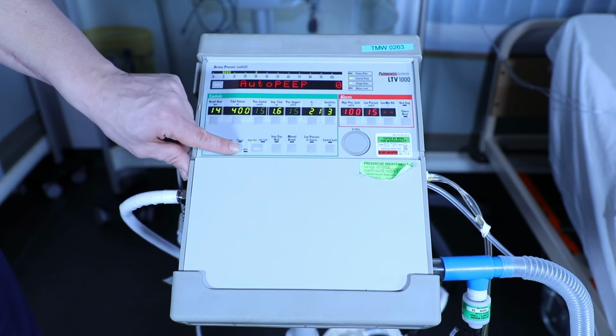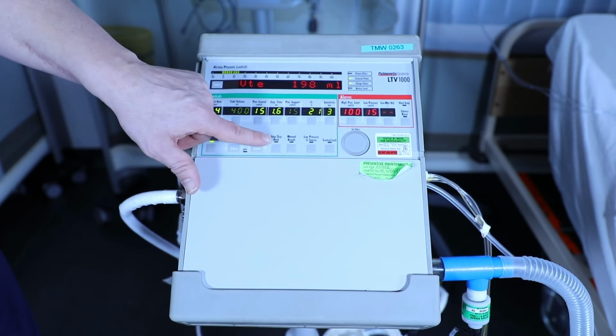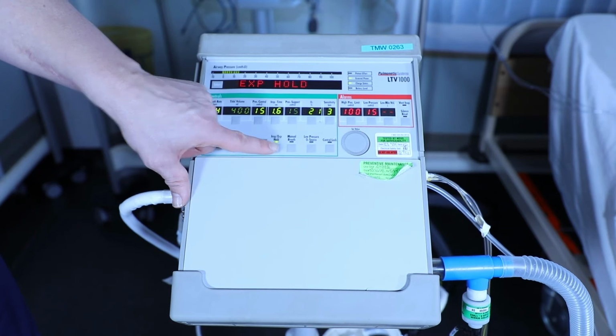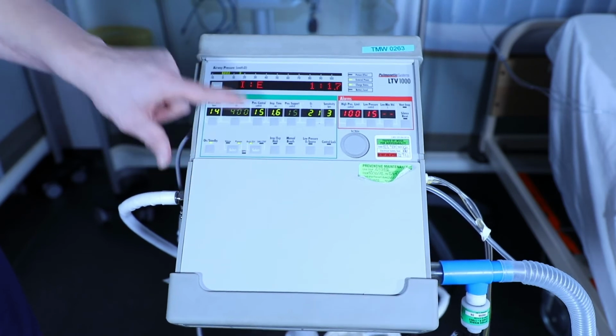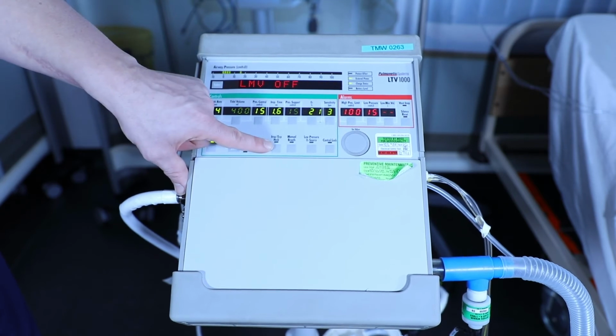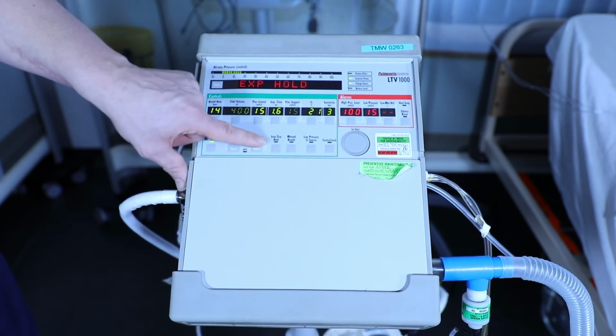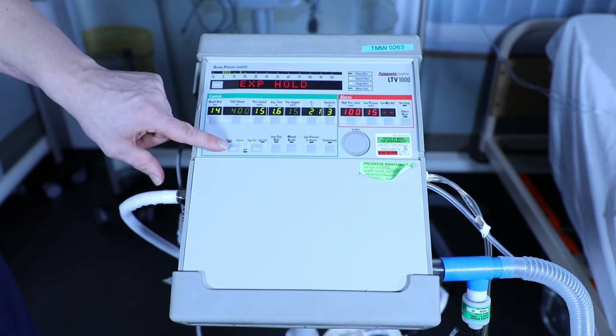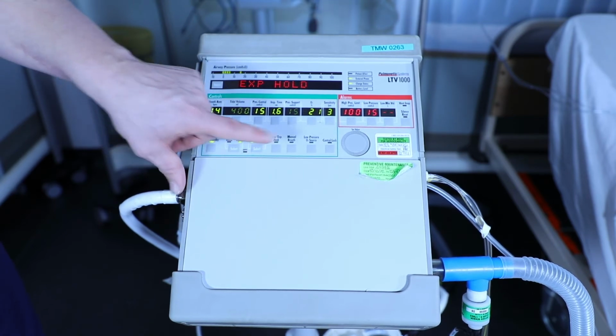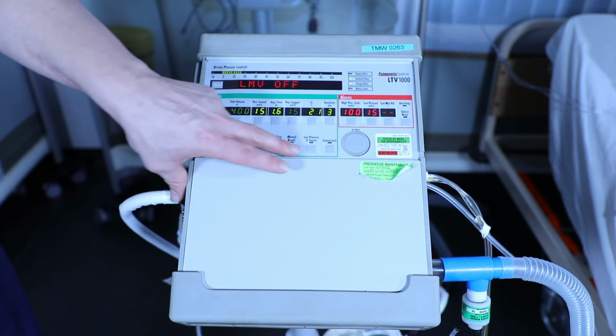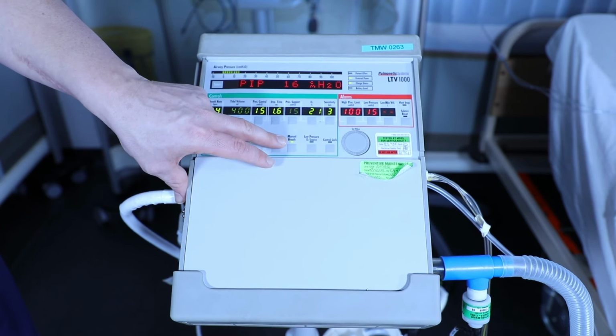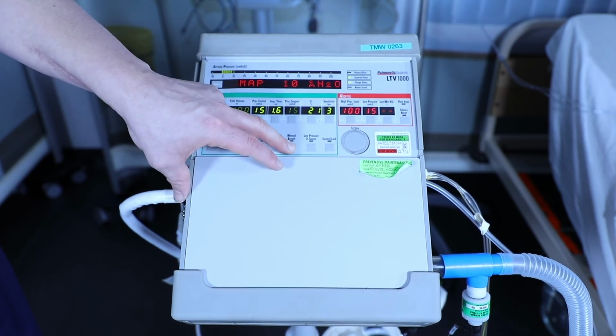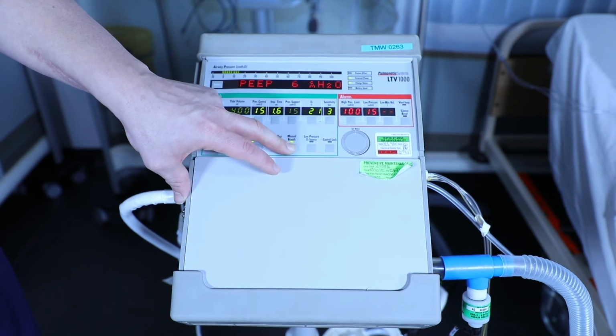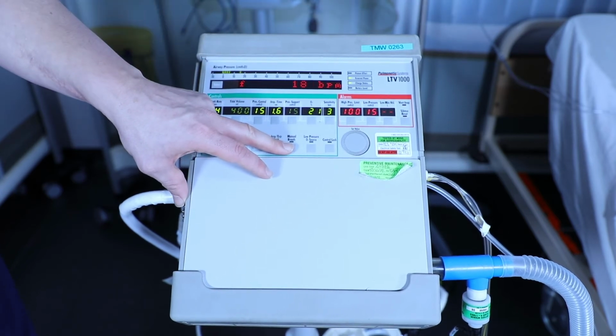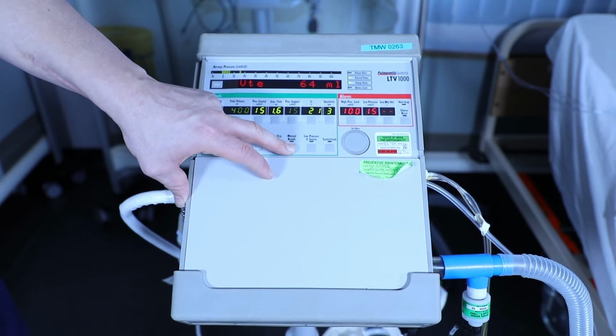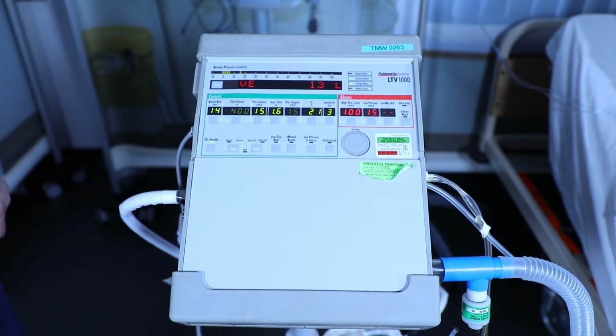To show that when we're in pressure mode, the only function available is an expiratory hold. So if we press, the first thing that appears is expiratory hold. If we press again, nothing, so it switches itself off. So we can only conduct an expiratory hold when we're in a pressure mode. To deliver a manual breath, we press, and when the LED illuminates, breath is administered. So we can see here, also with the real-time barograph, if we press that on expiration, that it also takes a breath.